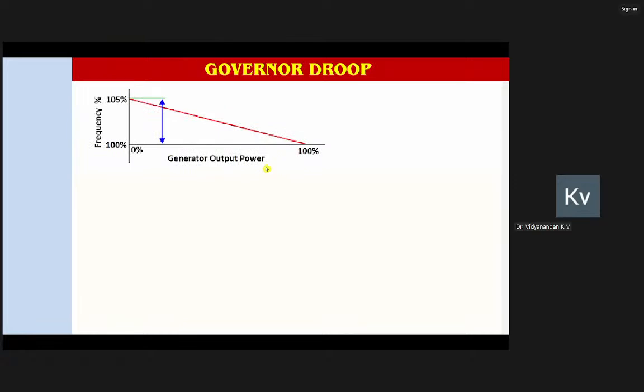Now, one of the important parameters which is working behind the screen, because that is a very silent parameter, is the governor droop. That is what we call the frequency influence. Whenever your machine is connected in parallel with any other machine, if it is a single machine connected with a single dedicated load, droop may not be necessary. But as long as two or more machines, because at utility level hundreds or even thousands of units are connected, droop is necessary, and droop is basically doing 2-3 activities. Now, what exactly is the droop?